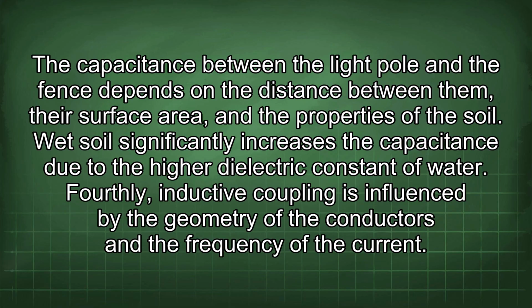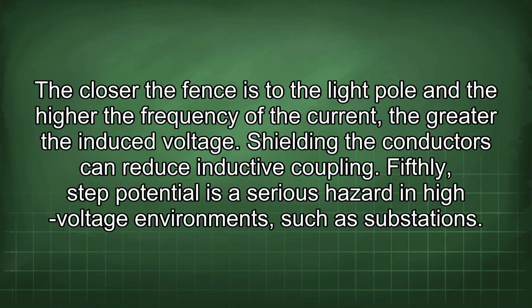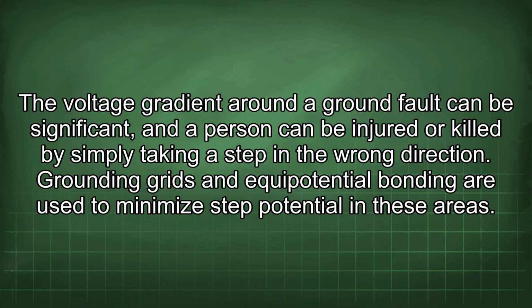Fourthly, inductive coupling is influenced by the geometry of the conductors and the frequency of the current. The closer the fence is to the light pole and the higher the frequency of the current, the greater the induced voltage. Shielding the conductors can reduce inductive coupling. Fifthly, step potential is a serious hazard in high voltage environments such as substations. The voltage gradient around a ground fault can be significant, and a person can be injured or killed by simply taking a step in the wrong direction. Grounding grids and equipotential bonding are used to minimize step potential in these areas.